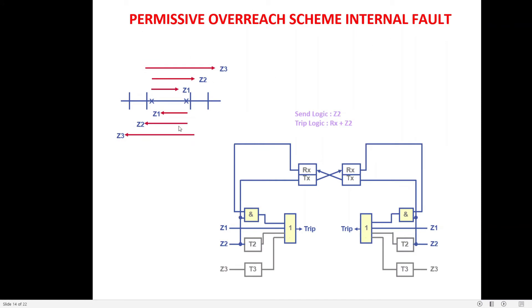Next is Permissive Over-Reaching Transfer Tripping (POTT). In this scheme, the carrier is sent using Zone 2 pickup. If a fault is in Zone 1 it will also be in Zone 2, so Zone 2 always picks up for Zone 1 faults as well. Because Zone 2 reaches 120% of the line, we must consider two cases: internal faults (80% to 100% of the line) and external faults (100% to 120%, i.e., on the adjacent line).